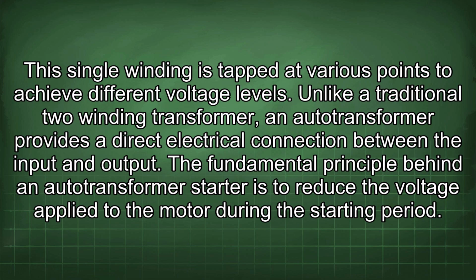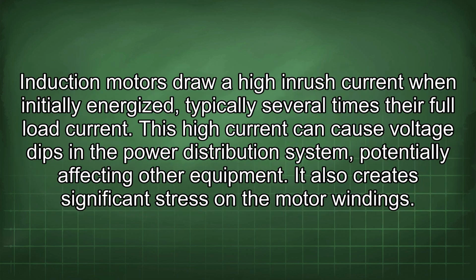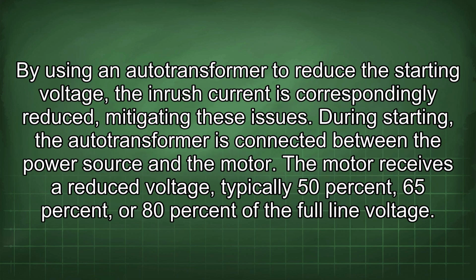The fundamental principle behind an autotransformer starter is to reduce the voltage applied to the motor during the starting period. Induction motors draw a high inrush current when initially energized, typically several times their full load current. This high current can cause voltage dips in the power distribution system, potentially affecting other equipment. It also creates significant stress on the motor windings. By using an autotransformer to reduce the starting voltage, the inrush current is correspondingly reduced, mitigating these issues.